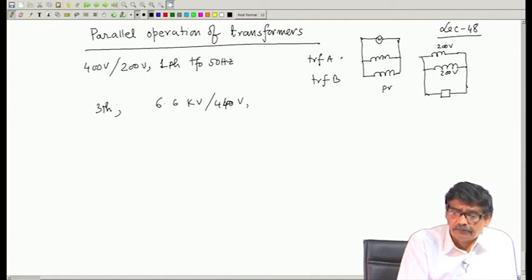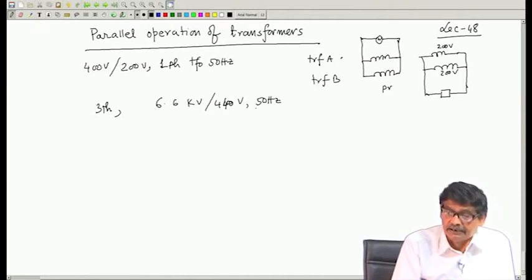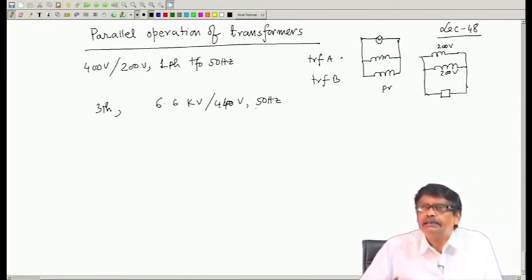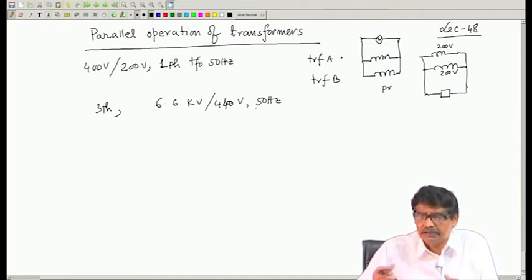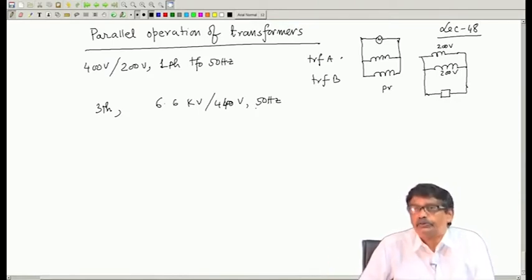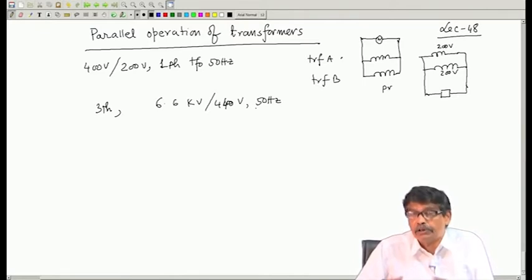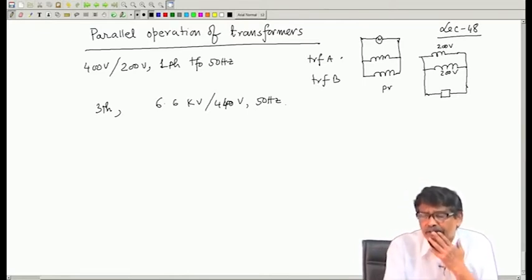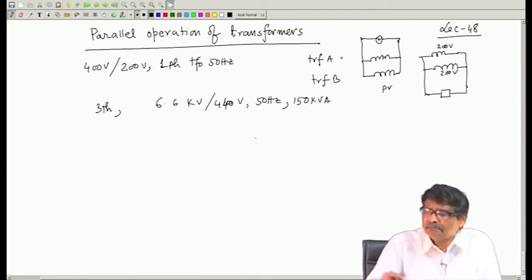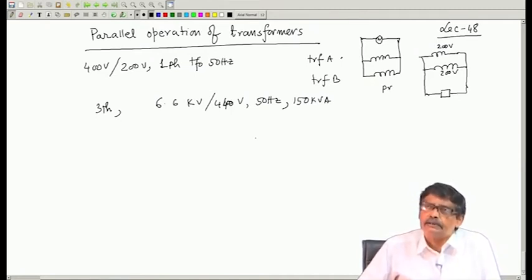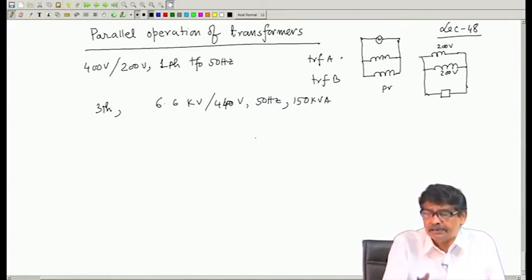It is also true for a 3 phase transformer, 3 phase 50 hertz. Now, suppose you see that presently the rating is say 100 kVA, which will be sufficient to cater to the consumers, because it is a growing area and load demand is growing. So, suppose you decide, okay, I will now buy a 150 kVA transformer, with 50 kVA as a margin, and start giving power to the consumers. But as you know, as the area is growing, every 5 or 7 years the load becomes doubled. Approximately, maybe after 10 years the power demand will become 300 kVA.